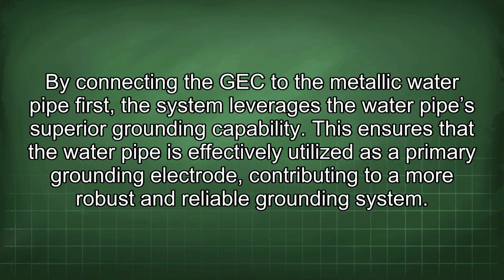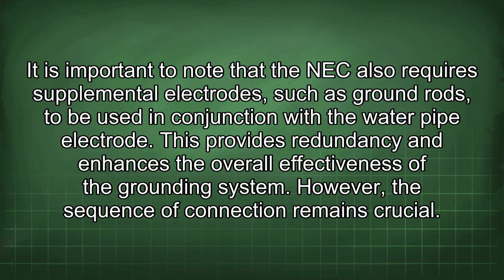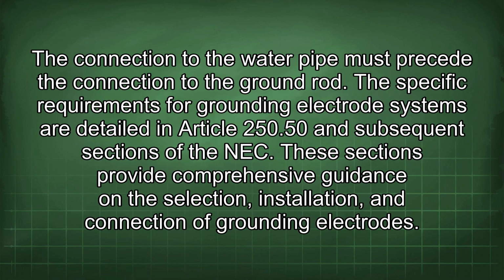By connecting the GEC to the metallic water pipe first, the system leverages the water pipe's superior grounding capability. This ensures that the water pipe is effectively utilized as a primary grounding electrode, contributing to a more robust and reliable grounding system. It is important to note that the NEC also requires supplemental electrodes, such as ground rods, to be used in conjunction with the water pipe electrode. This provides redundancy and enhances the overall effectiveness of the grounding system. However, the sequence of connection remains crucial. The connection to the water pipe must precede the connection to the ground rod.